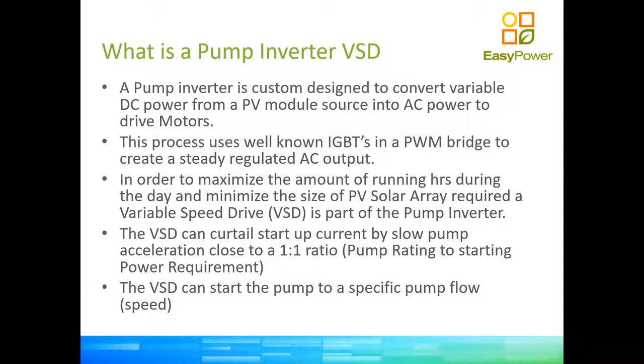The VSD allows us to start a pump with a limited amount of current by ramping up the frequency slowly over a 25-second period. We can have a one-to-one match between a VSD and a pump, depending on the depth and distance. The VSD can be programmed to a target pump flow — if we know the production charts of the pump and the height and flow versus RPM, that can be translated into frequency and the inverter can be set to a specific frequency point.